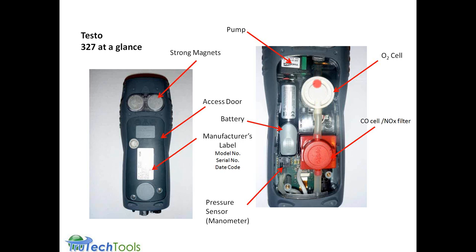You want to hook it to the inlet of the oxygen sensor and make sure it hooks up to the bridging tube that goes into the CO sensor, and then the CO sensor goes into the exhaust port. So the flow of gas is basically over oxygen, over CO, and then exhaust. So it comes in through the bottom of the meter, goes up through a series of channels into the water trap where the condensate's knocked out, pulled into the pump, exhausted by the pump, over here to the oxygen sensor, then over to the CO sensor, then back out the meter. So that's the path through the meter.